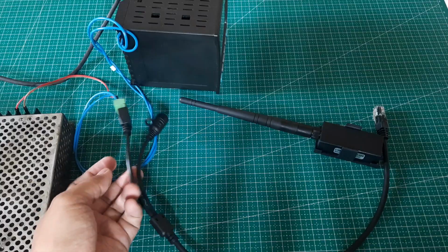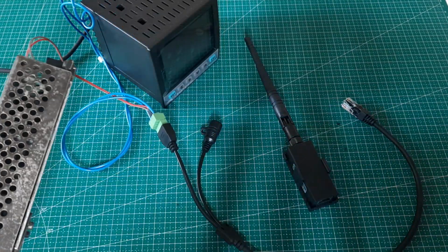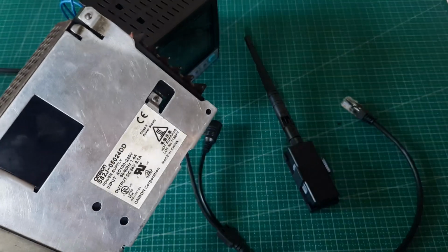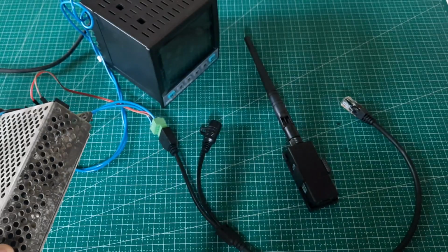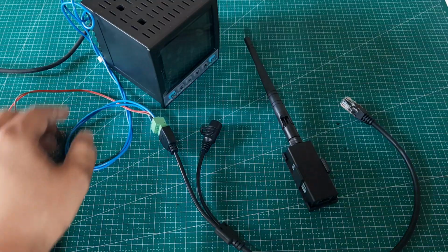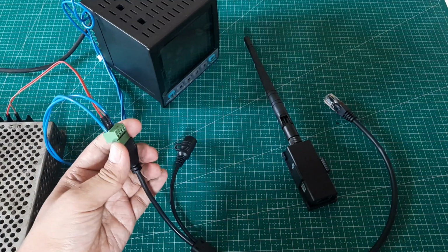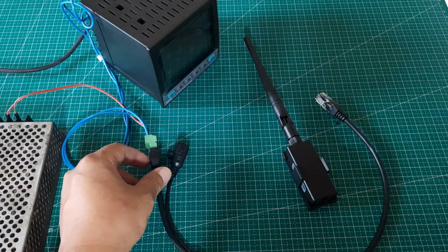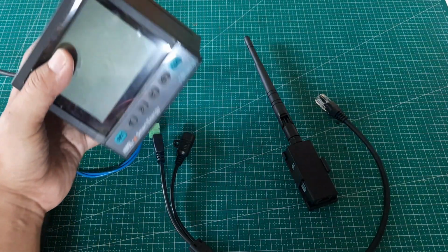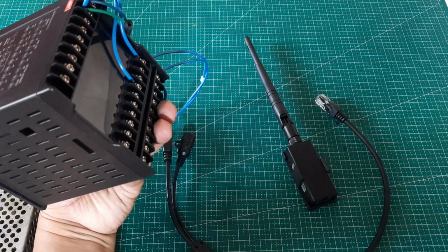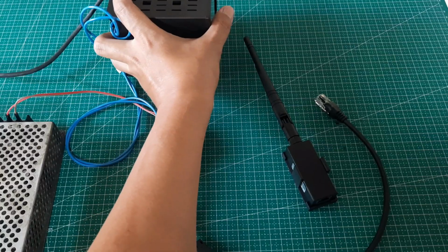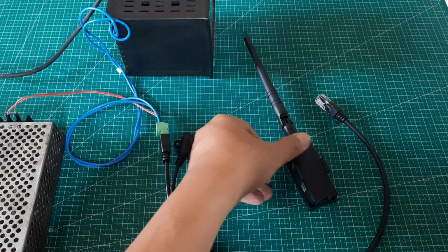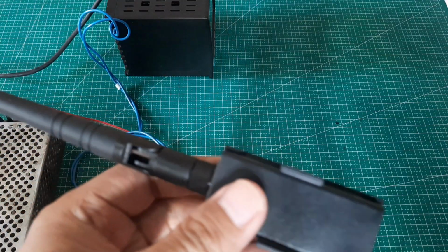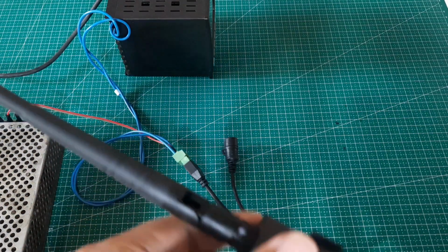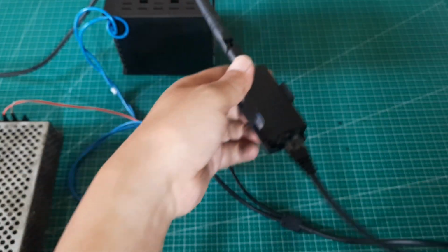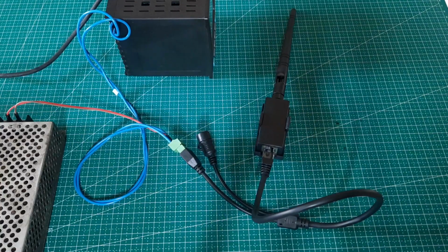In this tutorial, we'll be using a 24-volt power supply to power up the Elfin EW11A Modbus RTU to Wi-Fi adapter. The RS-485 terminals on the EW11A are connected to an energy monitoring device that communicates using Modbus RTU. In this example, we'll focus on reading just the voltage values from that device. The EW11A also comes with an Ethernet port, which can be used during the initial configuration or as an alternative wired connection. Once the setup is complete, the EW11A will convert the Modbus RTU signals into TCP/IP packets and send the data over Wi-Fi, allowing us to monitor the Modbus device wirelessly without long serial cables.